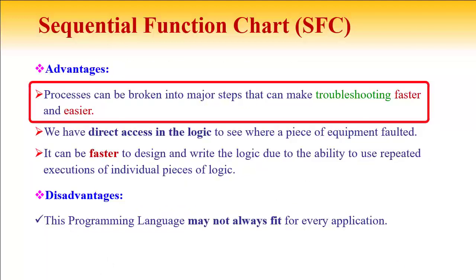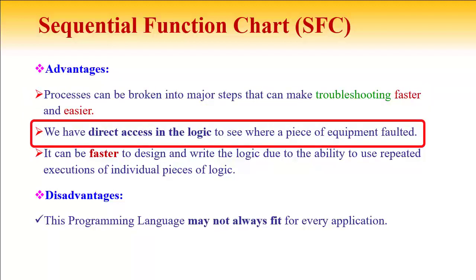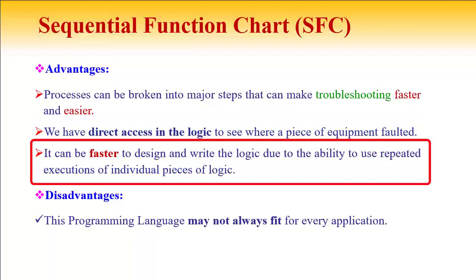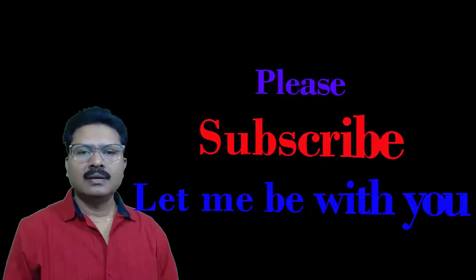Advantages of Sequential Function Chart: the process can be broken into major steps, making troubleshooting faster and easier. We have direct access in the logic to see where a piece of equipment faulted. It can be faster to design and write logic due to the ability to use repeated execution of individual pieces of logic. Disadvantage: this programming language may not always fit every application in a process control system.